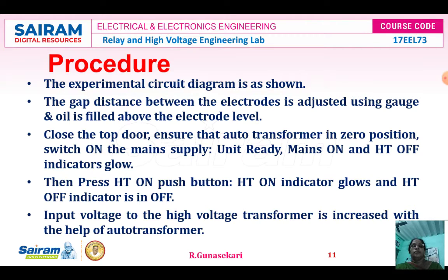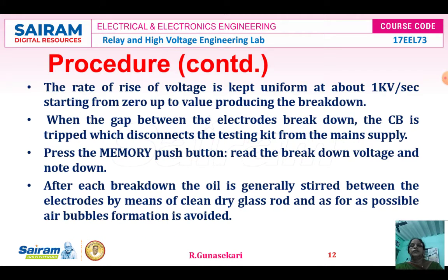Now switch on the main supply. Unit ready, mains on and HT off indicators glow. Then press HT on push button. Now HT on indicator glows and HT off indicator is off. Input voltage to the high voltage transformer is increased with the help of variac. The rate of rise of voltage is kept uniform at about 1 kV per second, starting from 0 up to the value producing breakdown between the electrodes.